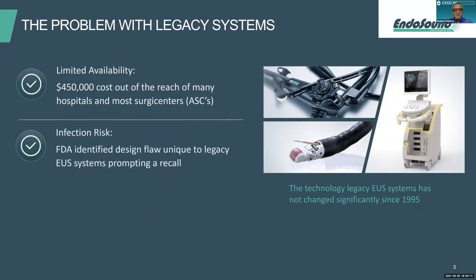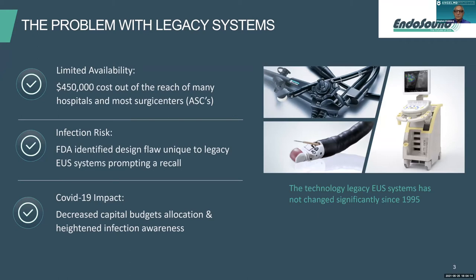So what's the problem with legacy systems? The legacy systems shown here include a big box solution for the beamformer and a designated endoscope that has a transducer on the end of it. This combination is a $450,000 lift, which is a big ask these days in a time of limited capital budgets. If that weren't enough, there's an infection risk conferred by a design flaw in these endoscopes, for which the FDA has issued a recall for all of Olympus's echo endoscopes. Lastly, in the COVID era, decreased capital budgets make the ability to do capital purchases a much more difficult circumstance.